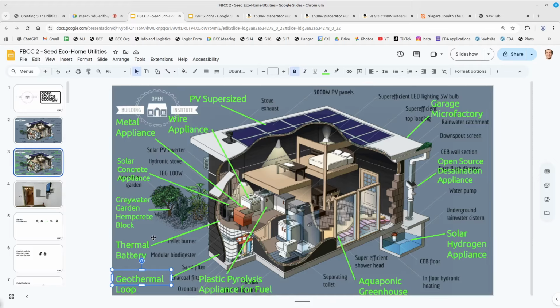Now for thermal battery, this is our cunning plan. We're going to build a separate 10 by 12 building module that attaches to the back of the house, where we'll put a bunch of biodigester totes, cooling and heating the water in there up to 120°F and down to whatever cooling temperature is, whatever the heat pump puts out on the cold side, so that we can heat exchange it. We can heat in winter, cool in summer.